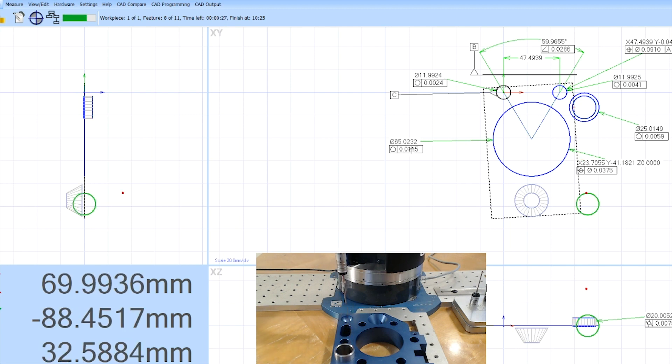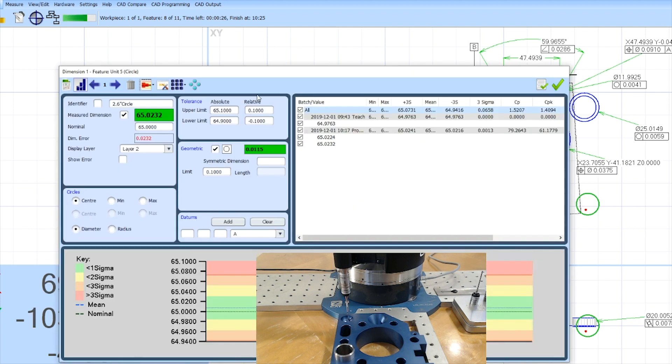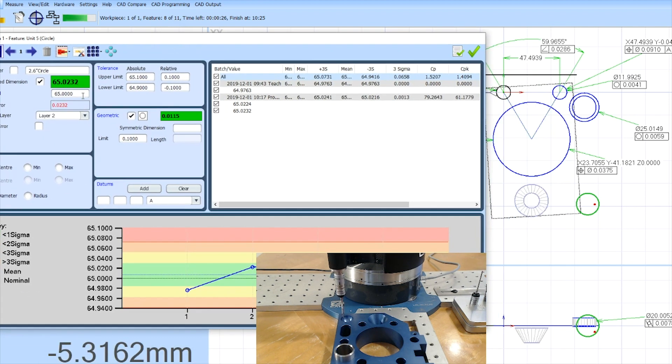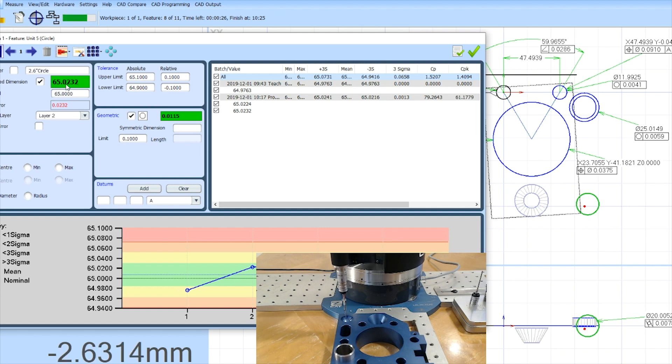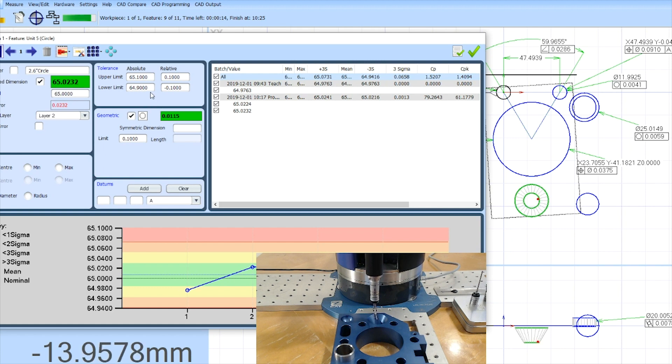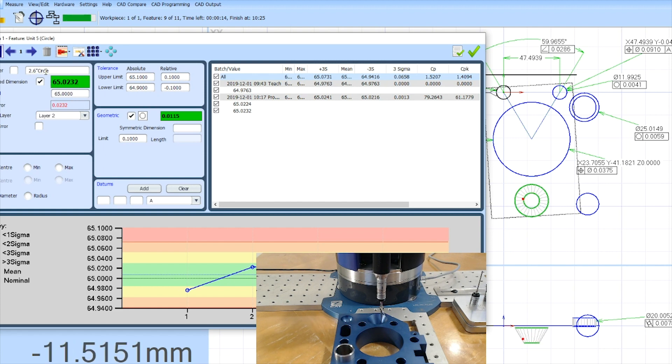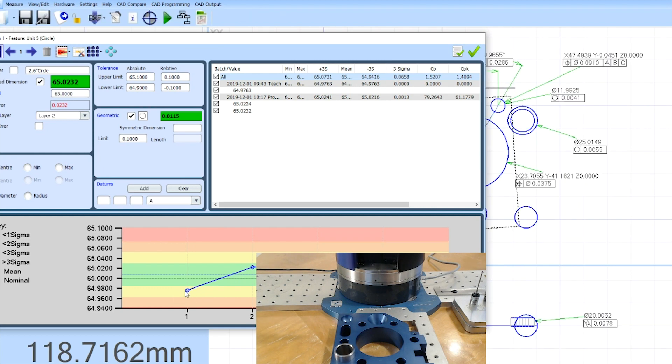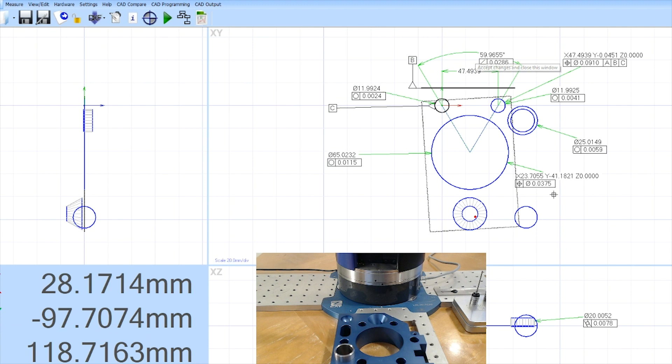So once I pulled out the dimension, in this case the large diameter, if I look at it, you'll see it's assuming the nominal is 65 millimeters based on what we measured. And then it puts in the tolerances plus or minus whatever we normally have. It will fill those in and check if they're within tolerance. We can edit the tolerance. We can edit the nominal. We can edit the identifier. We can put in bubble numbers. You can see here, it's measured this part three times. The first time we measured it manually, we got 64.9763. We've done it twice now under DCC. It's 65.022, 65.023. That's one micron difference between those readings sitting on my wooden desk. So all of the things are updated here.